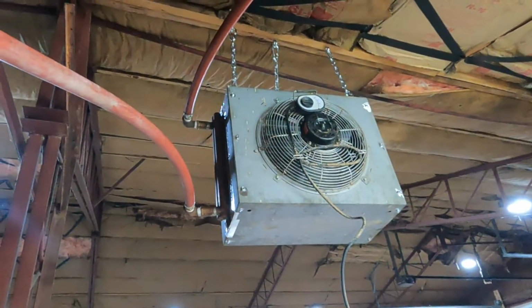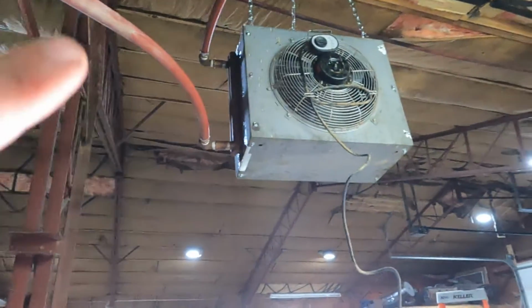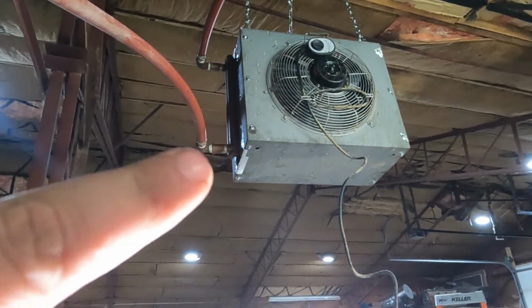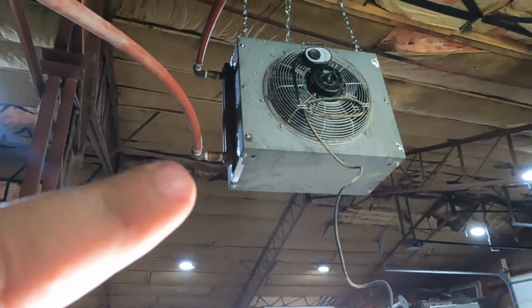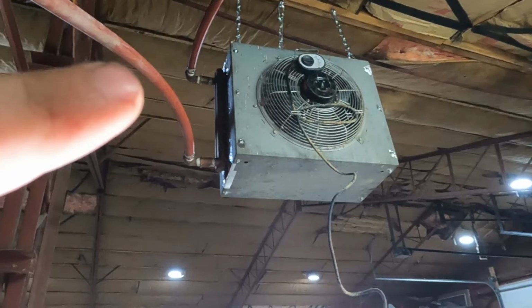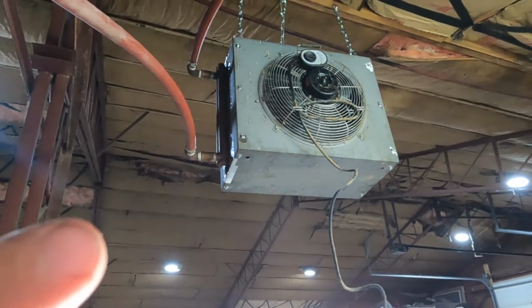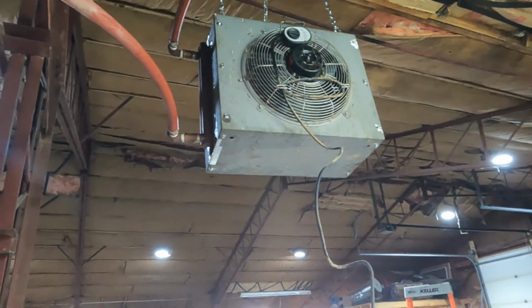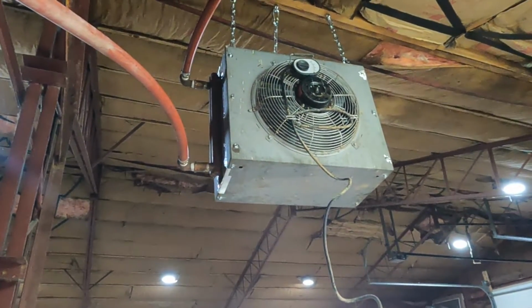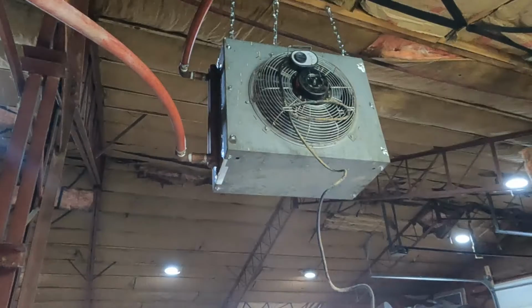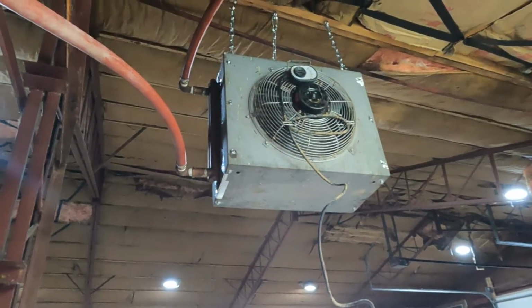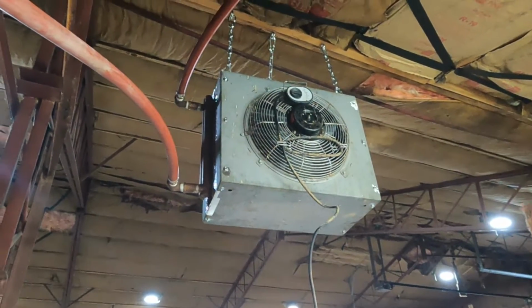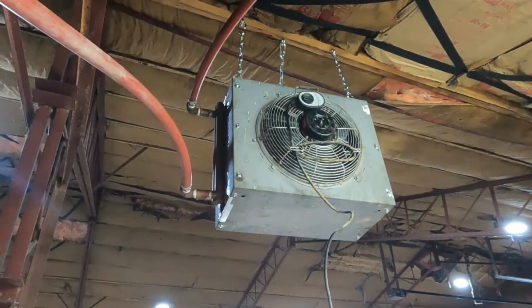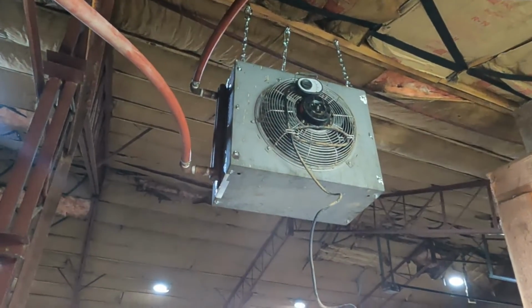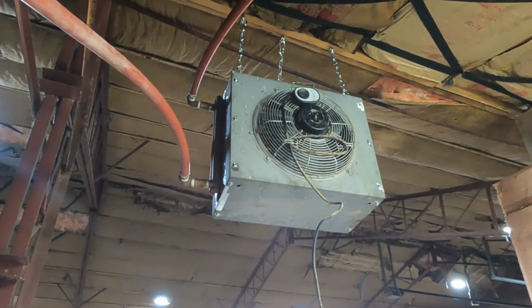Your pump will go to your bottom. So that fitting right there, the bottom of your heat exchanger, the bottom of your radiator, is where your inlet will go, and the return to your boiler will come out the top. That way when the water fills the radiator and it's flowing through, it pushes any air bubbles or air pockets out. If you put the water in the top, the water will just fall down the tubes in the heat exchanger and it can aerate and get bubbles the whole way, and those bubbles will wreak havoc with your pumps. The pump side will go in the bottom, and you'll push up any air or any pockets.